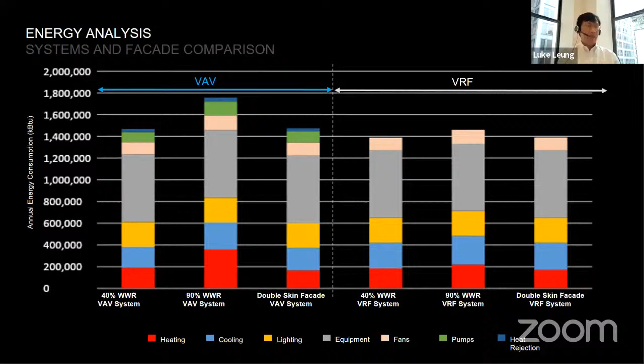This is the energy analysis of VAV versus VRF, and VRF is better here mainly because of heating. Also, under part-load conditions, the VAV system still has to run the big fan floor by floor, but with VRF we can isolate just the area that needs it. So part-load operation in smaller units, plus the heating advantage, is why VRF comes out ahead.